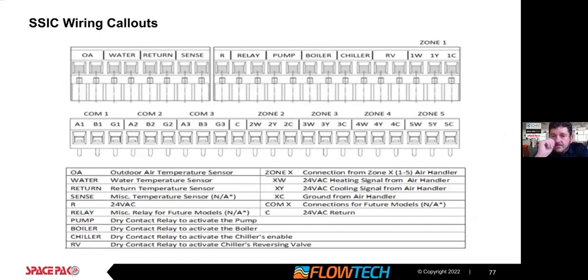Here's a diagram showing the control board, and we can get into it too, but your outdoor sensor plugs in here, buffer sensor here. These are your zones, your heating and cooling zones over here, and your reversing valve right here. So this will be what tells the outside unit to go into heating or cooling mode based on the call.